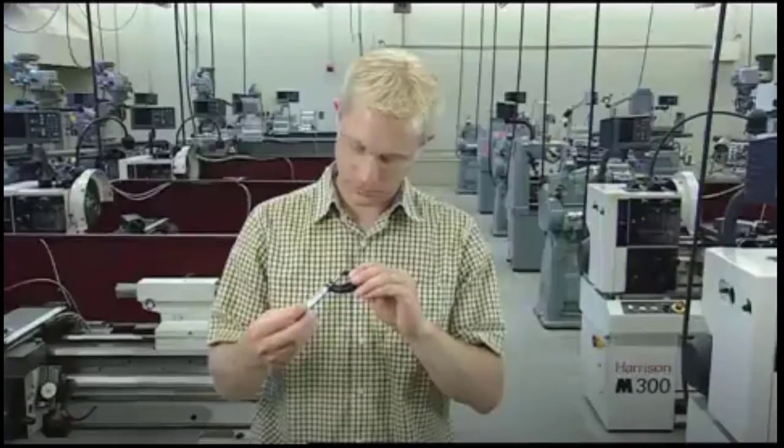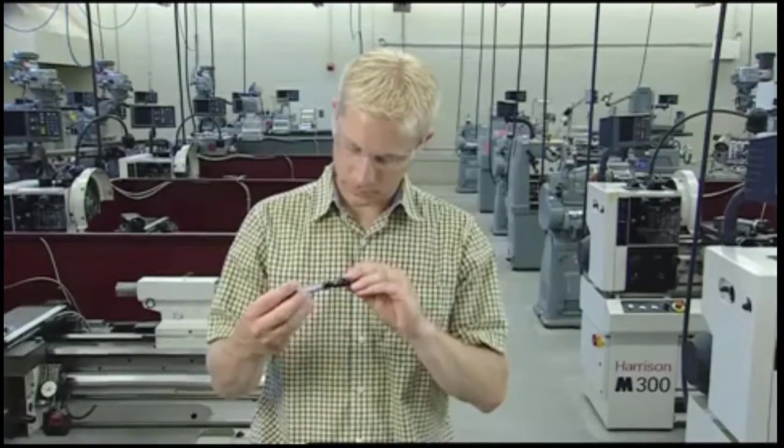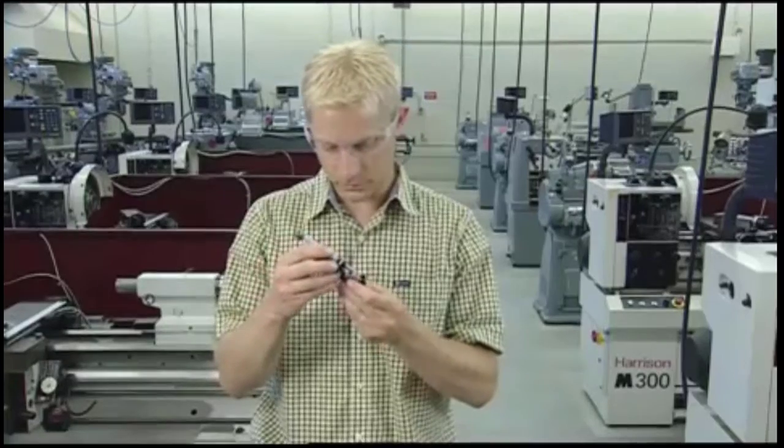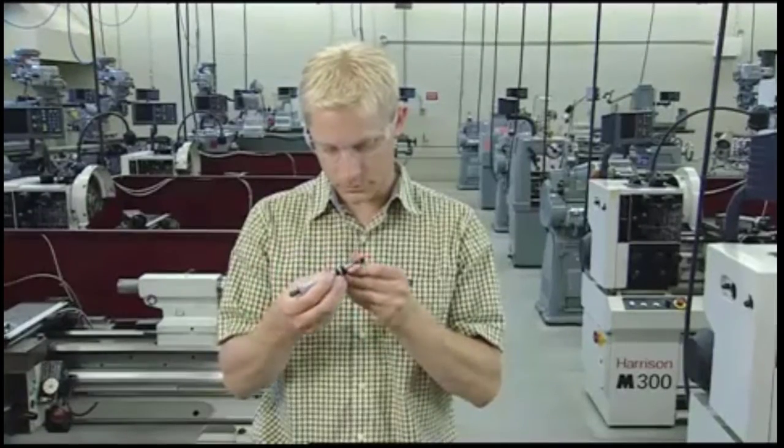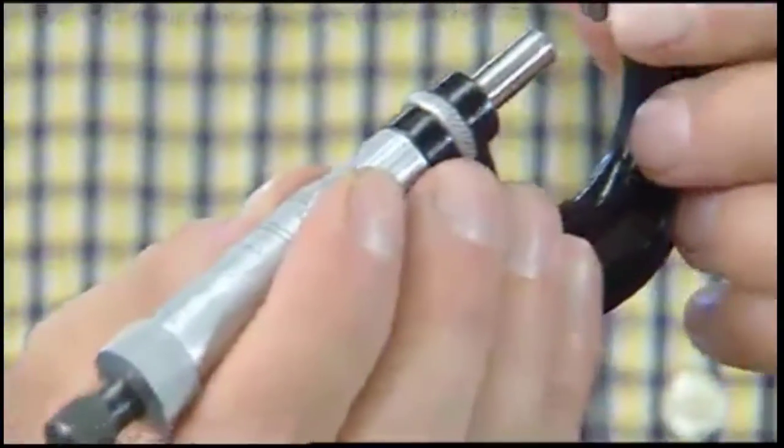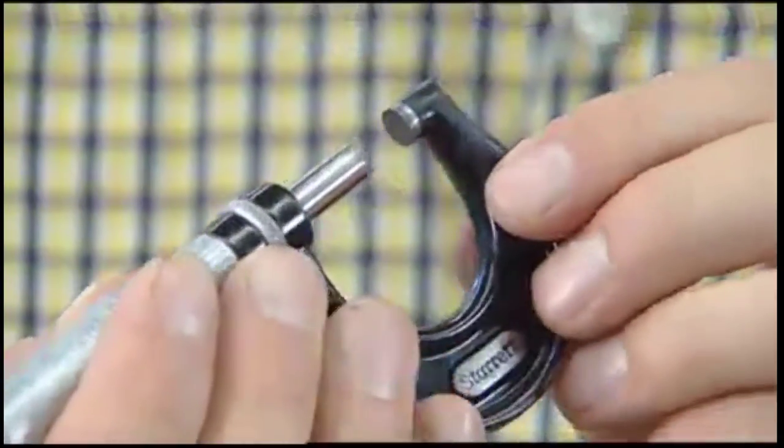To calibrate a micrometer, begin by visually inspecting both the spindle and anvil faces for chips, cracks, and wear. If you find any severe damage, properly dispose of the micrometer.